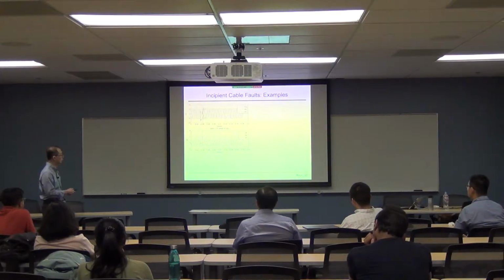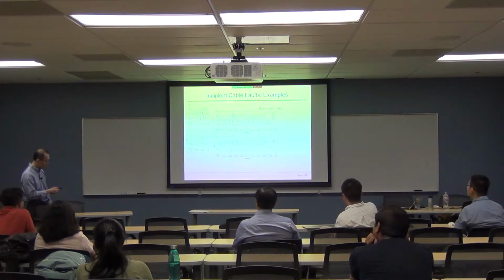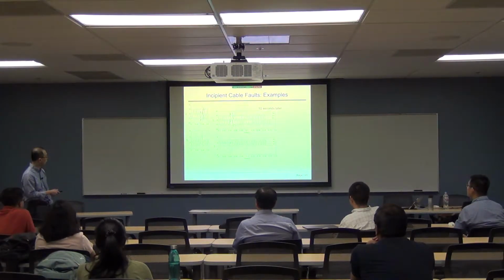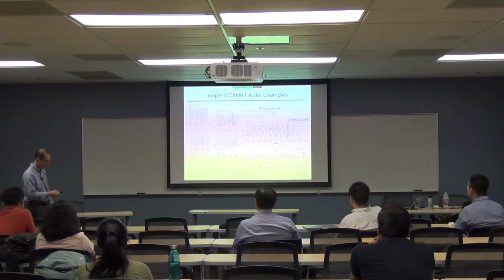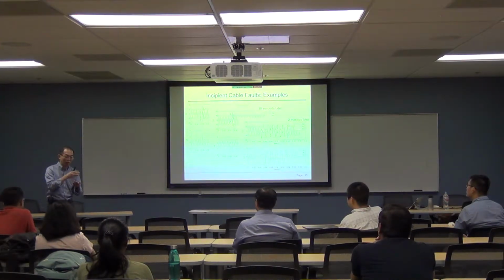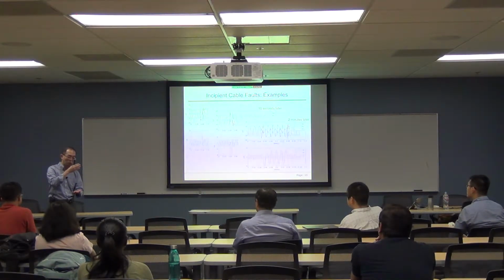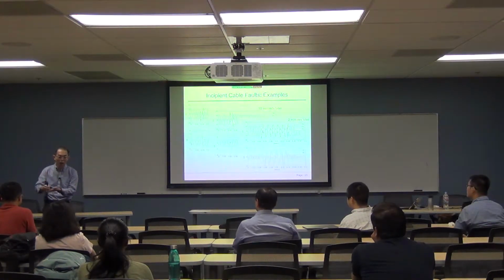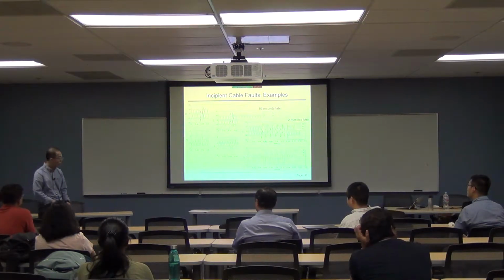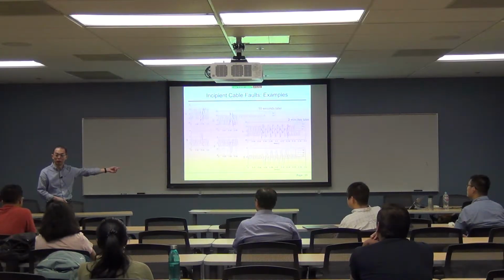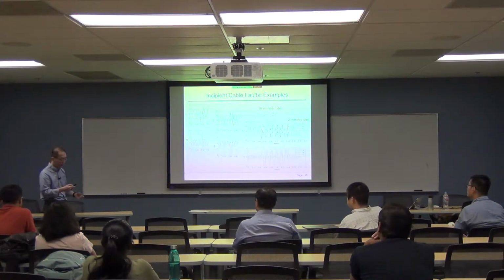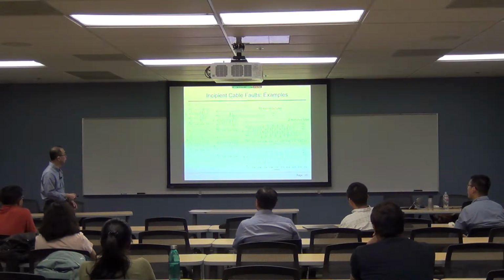Now, this is an example. You can see that there is one here. And then 10 seconds later, another one happens here. So this is phase A. And then another one later, this is 2 minutes later. So the way that it progresses, we tend to say that it happens at increasing frequency, maybe every week, and then every few days, every hour, minutes, and then finally it blows. It's not that clean, okay? It can happen like 10 seconds and then 2 minutes later. We never know. It's almost random, okay? Therefore, the algorithm has to be very, very robust, okay?